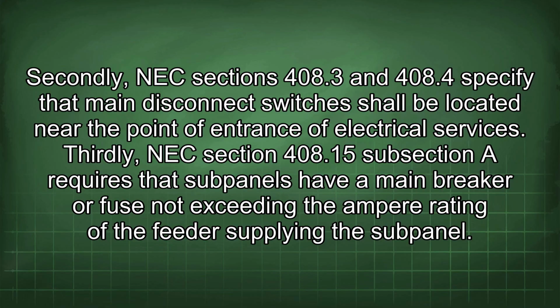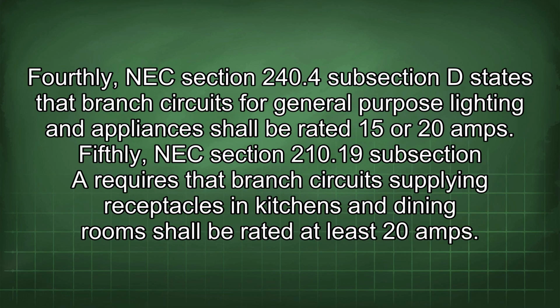electrical services. Thirdly, NEC Section 408.15 subsection A requires that subpanels have a main breaker or fuse not exceeding the ampere rating of the feeder supplying the subpanel. Fourthly, NEC Section 240.4 subsection D states that branch circuits for general purpose lighting and appliances shall be rated 15 or 20 amps. Fifthly, NEC Section 210.19 subsection A requires that branch circuits supplying receptacles in kitchens and dining rooms shall be rated at least 20 amps.